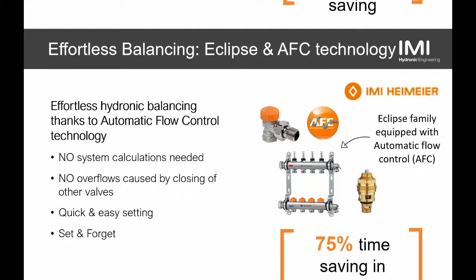Tired of system calculations for the mostly very large radiator plants? AFC technology will let you forget these worries in no time. Setting the correct flow is done by setting the valve on a scale from 1 to 15, where 1 is 10 liters and 10 is 100 liters.